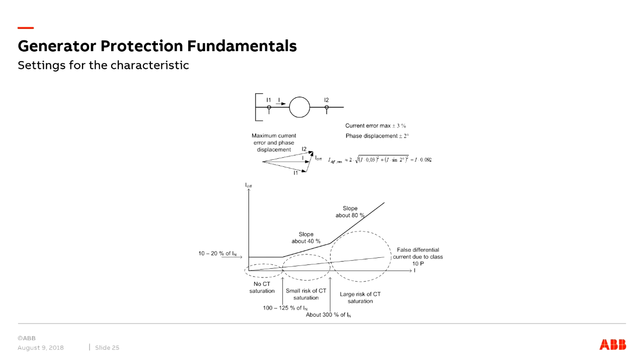Again, the typical settings here for this characteristic. Section 1, the operation level, the normal setting is within the range of 10 to 20%. This is a place where there is not much CT saturation. If we consider a maximum current error in the opposite direction of the CTs on each side of the generator, this can result in a false differential current, as shown in the figure, of about 10% of the generator current. In section 1, there is no risk of CT saturation.